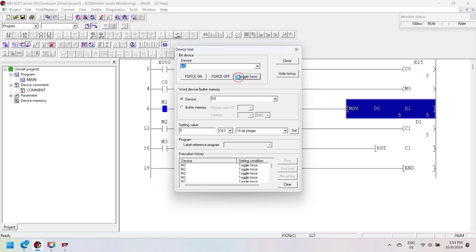The RESET instruction resets the counter value if the input is activated. If input M3 is activated, then counter C1 is reset. The RESET instruction only resets the counter current value, not the preset value.